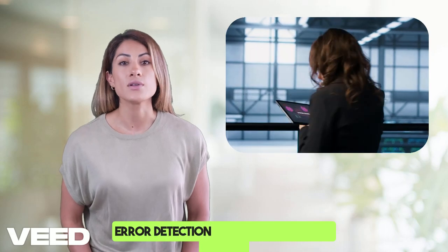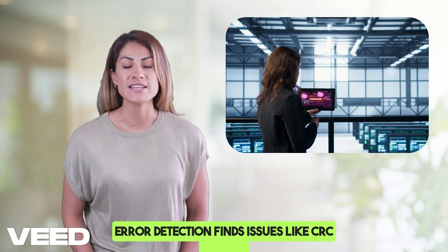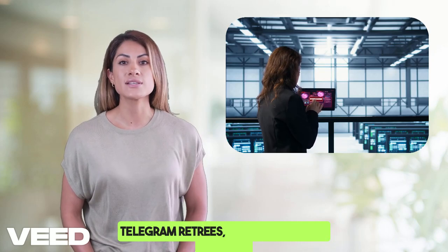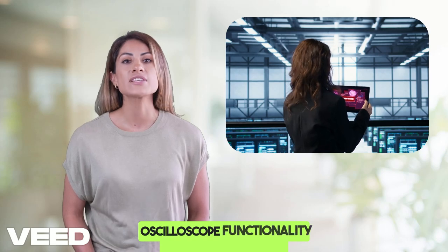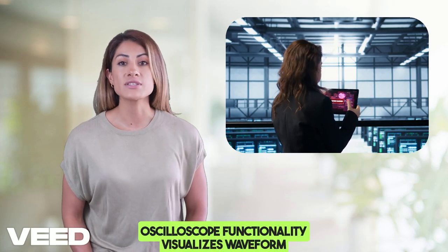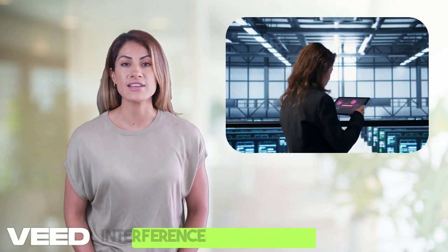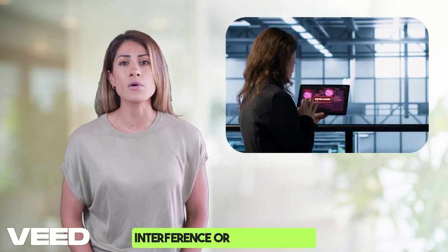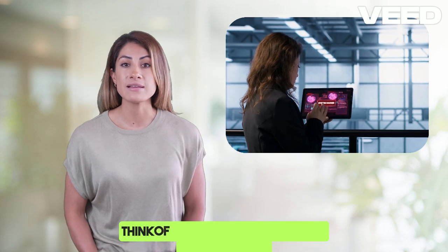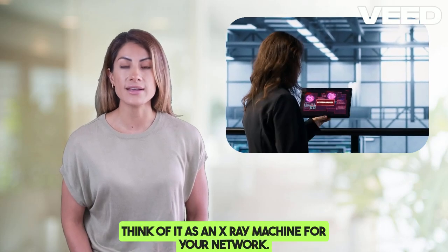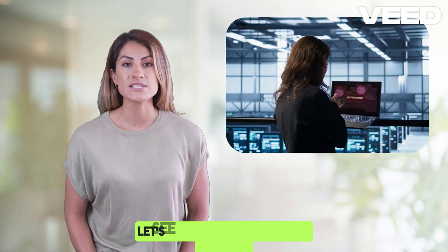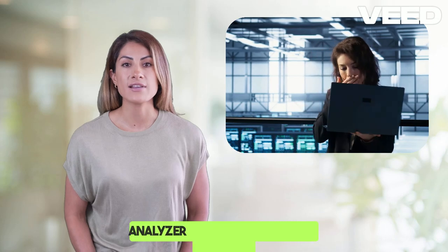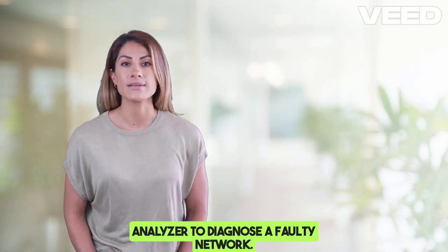Error detection: finds issues like CRC errors, telegram retries, jitter, and device failures. Oscilloscope functionality: visualizes waveform signals to identify electromagnetic interference, EMI, or bad shielding. Think of it as an X-ray machine for your network. It reveals hidden problems instantly. Let's see how engineers use a Profibus Analyzer to diagnose a faulty network.